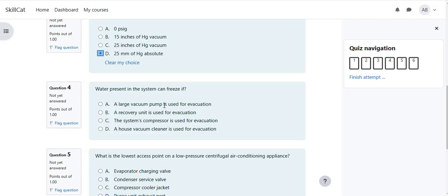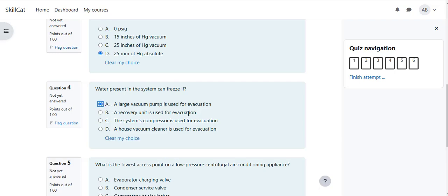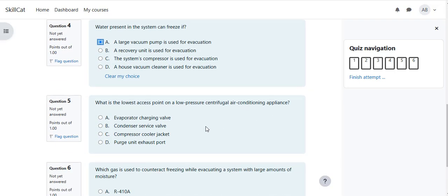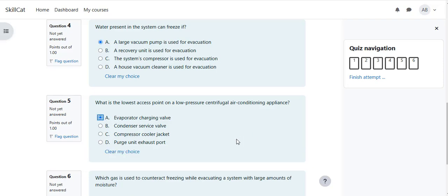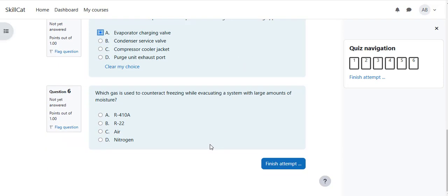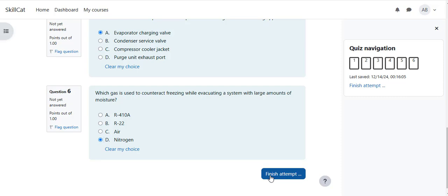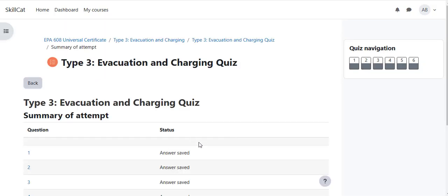Okay, a large vacuum pump is used for evacuation. What is the lowest access point on low pressure centrifugal air conditioning appliances? Evaporator charging valve. It's the lowest access point. Which gas is used to counteract freezing while evacuating a system with a large amount of moisture? It's nitrogen. It's used to counteract freezing.